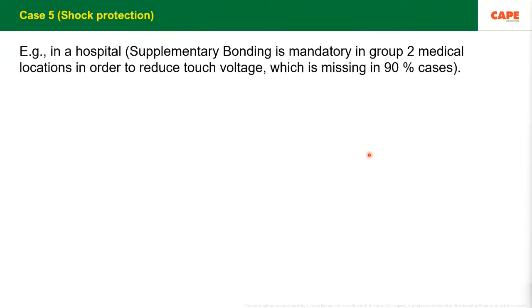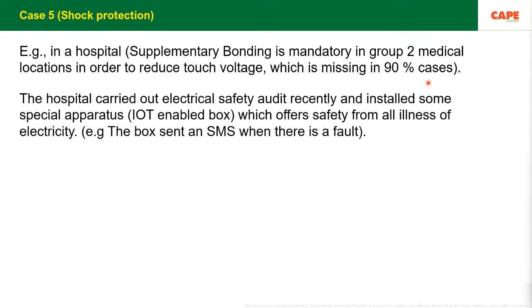Unfortunately, in the system which we checked in a hospital, this interconnection, called supplementary equipotential bonding, is necessary in a group 2 medical location. Means in an operation theater, shock hazard is more dangerous because a lot of metallic items are bypassing the skin, and resistances are lesser. You need to have a very, very high safety measure. Supplementary equipotential bonding is necessary. Unfortunately, this system is missing in almost 90% of the cases. During the last 2 years, I have visited at least 30 to 32 hospitals for making audits, and in 90% of cases this is missing.